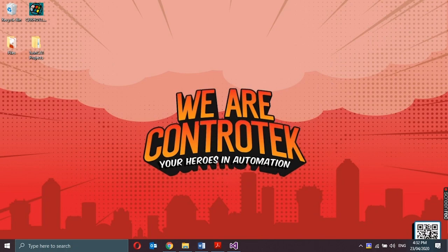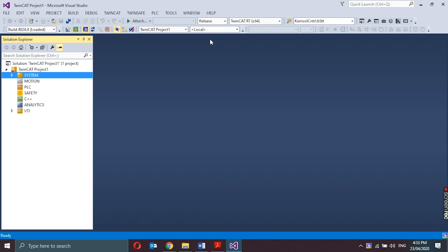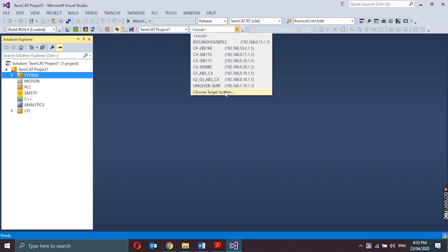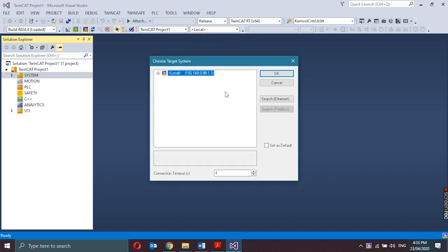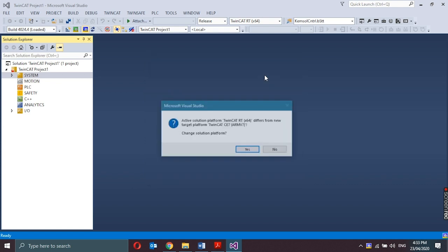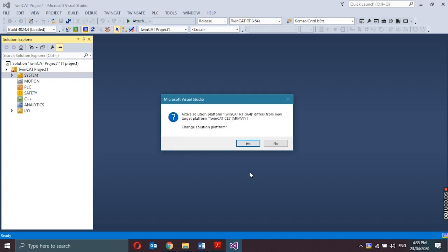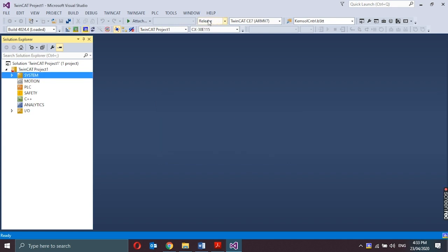After verifying that my computer has a good connection with the target device, I'll now go back to my TwinCAT project and select the correct target system. Currently, the selected target system is on local or my computer. What I need to do is select the CX-9020 as my target system here in the TwinCAT engineering environment. To do that, just click on here, choose target system, click choose target system again, drop down the local, and I could see that the CX-9020 is currently available here. Click on OK. It will ask you if the active solution platform should be changed. Just click on Yes. It's important not to miss choosing the correct target system.